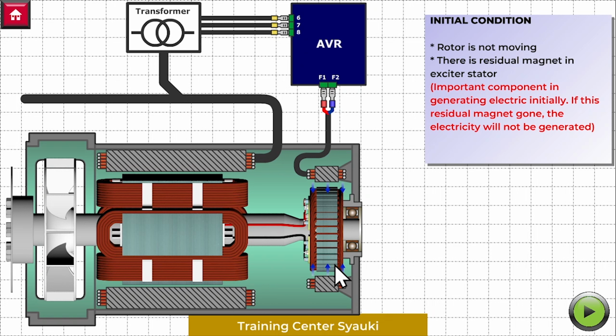I forget the English word... illustration, sorry. This blue arrow is not the illustration line of the magnet; it represents energy flow, from the exciter stator to the exciter rotor. The important component in generating electricity initially is this residual magnet. If this residual magnet is gone, electricity will not be generated. If you run the engine until the fuel tank is empty, there will be no electricity from this generator.